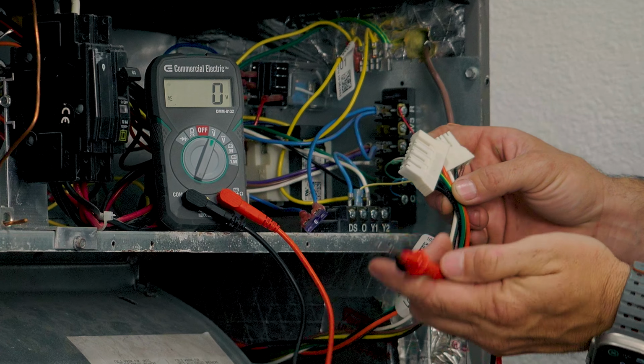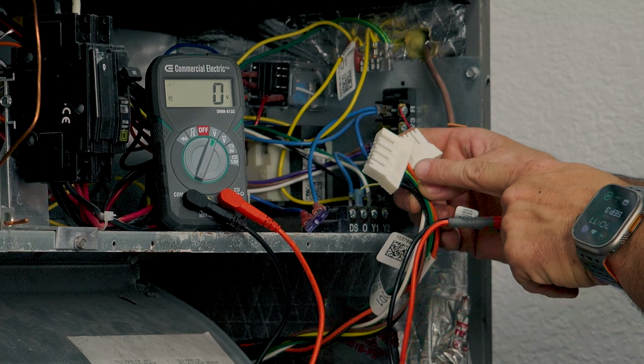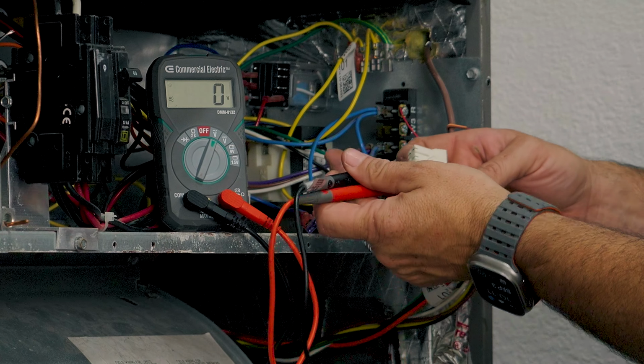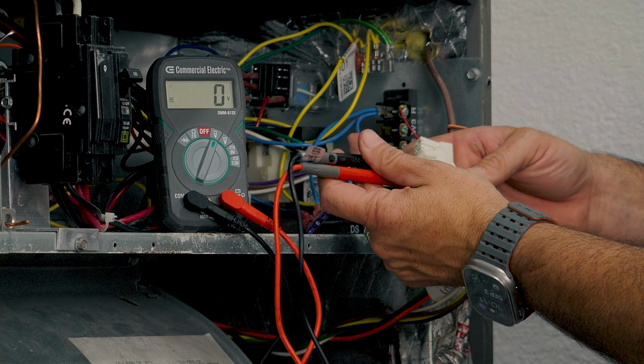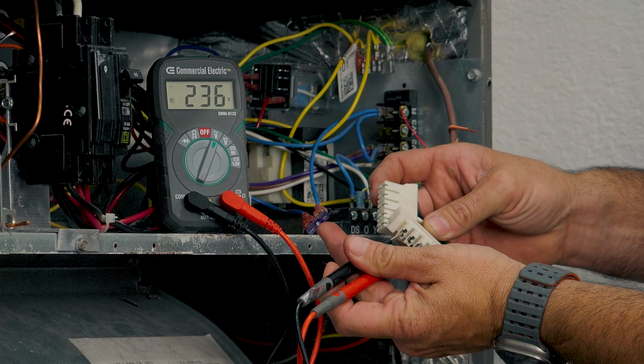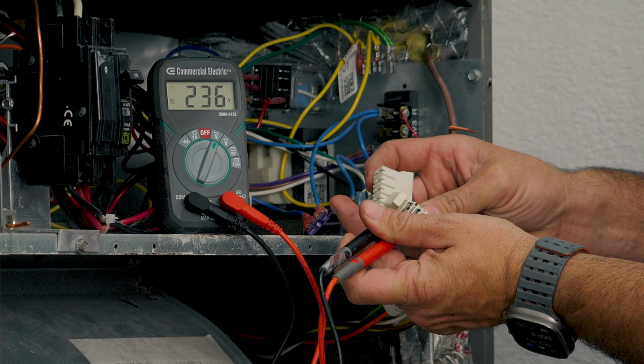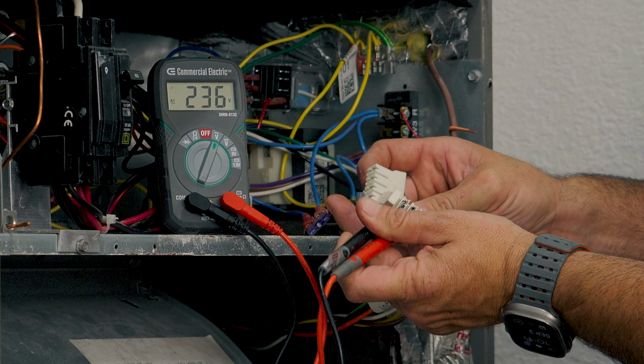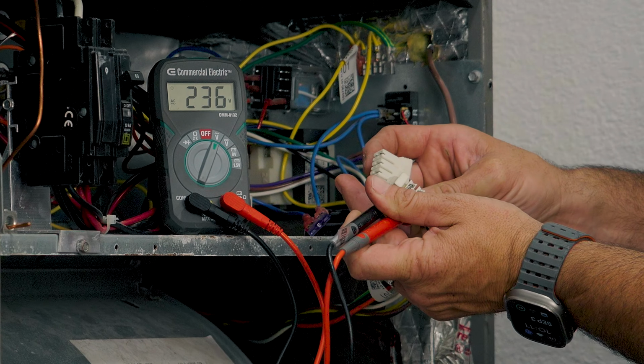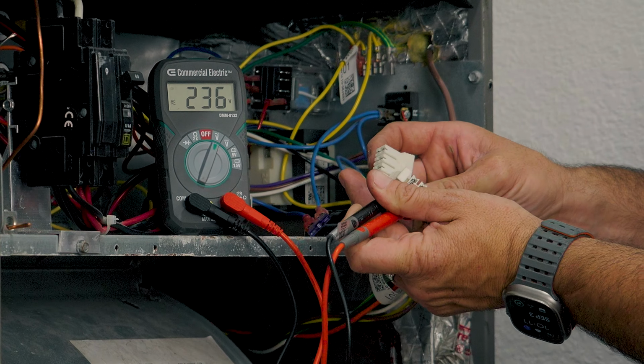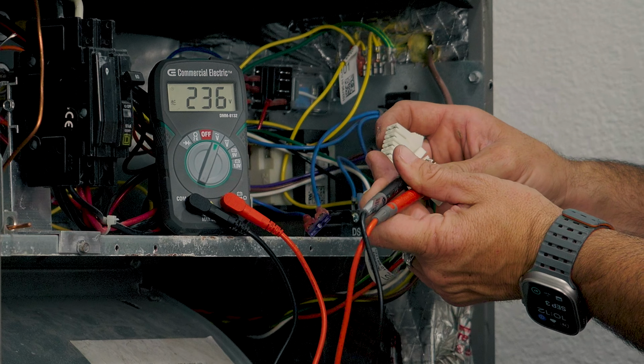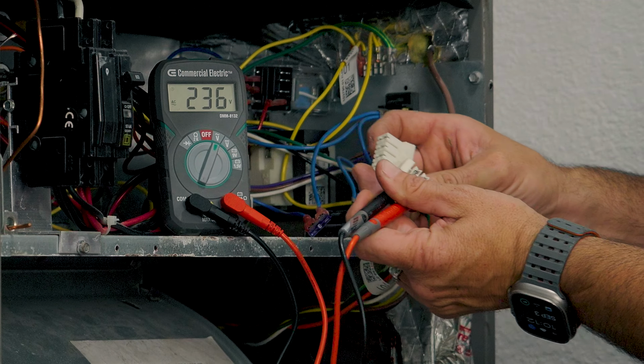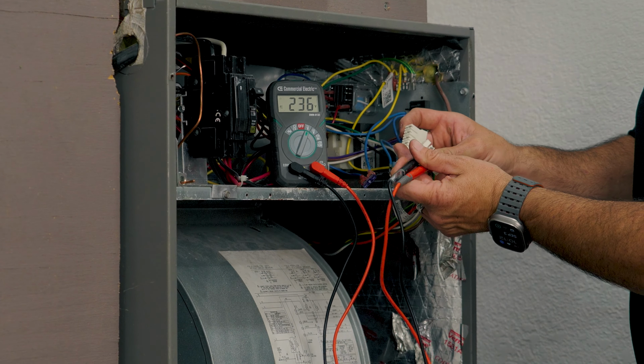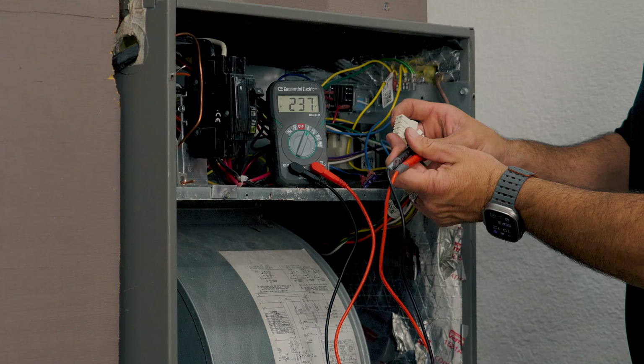We're going to use our tester on voltage AC and test between the L and the N. I'm getting 236 volts. This is a 220 volt system, so this is correct. You may have a 110 volt system, and you'll see something between 110 to 120 volts in that situation. If you do not see voltage here, you need to troubleshoot your system and find out why it is not receiving power.